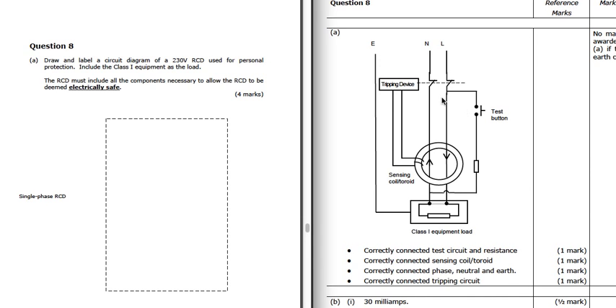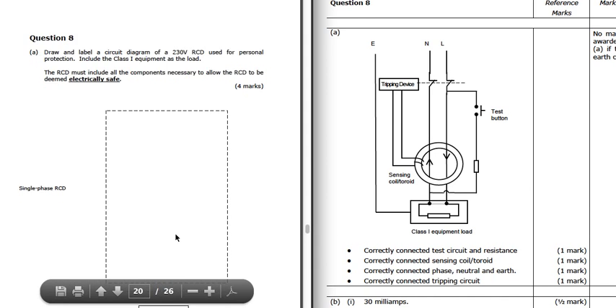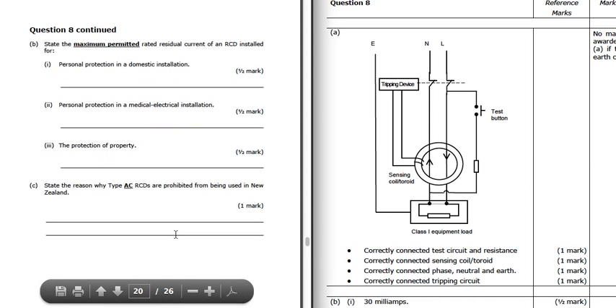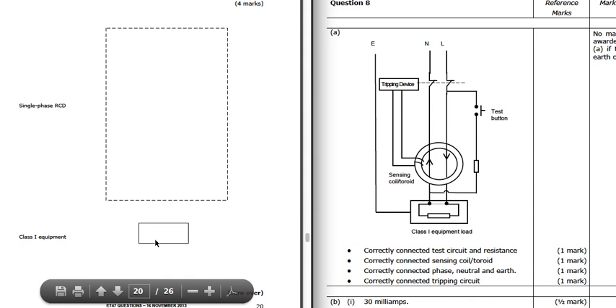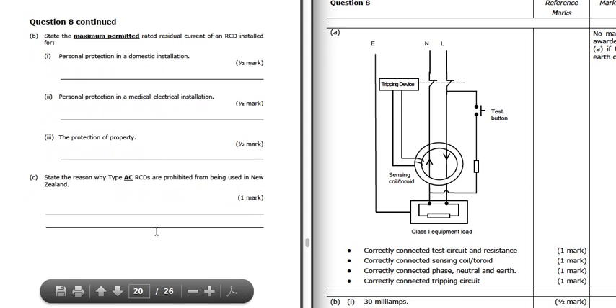And we've got a test button here between live and neutral with a resistor in there. So what that will do is when we press that test button, we'll get a small leakage of current because of this resistance, and this will set up an imbalance within the toroid, which the tripping device will see, and it will trip here. So they've drawn the class 1 equipment there.